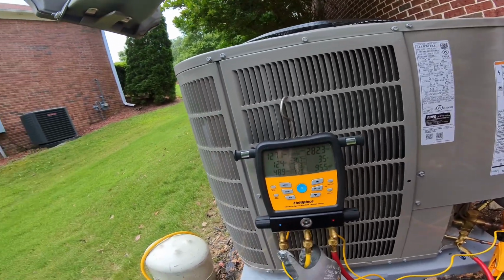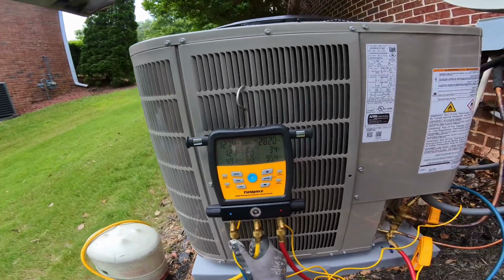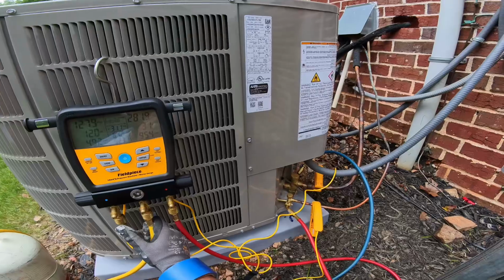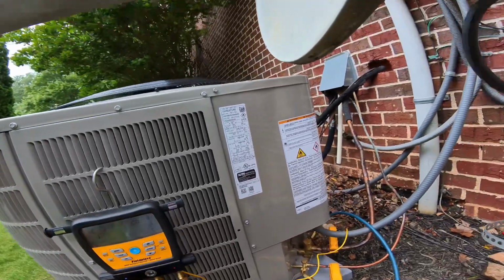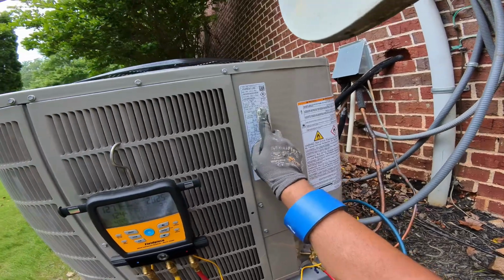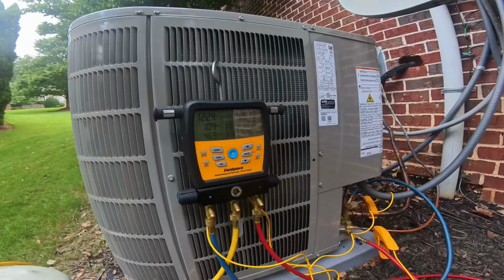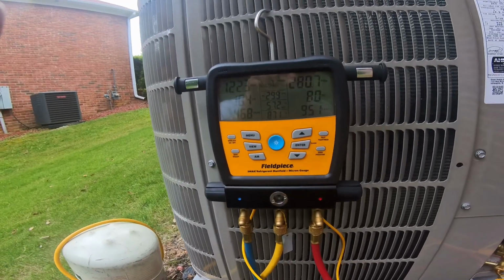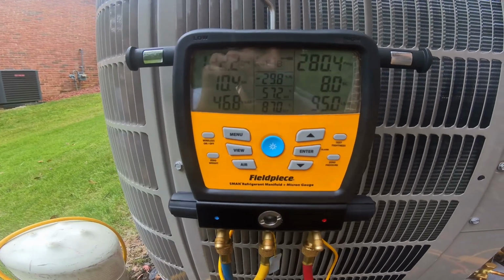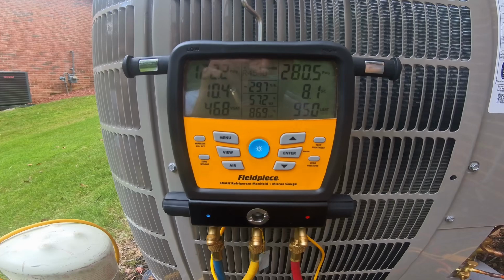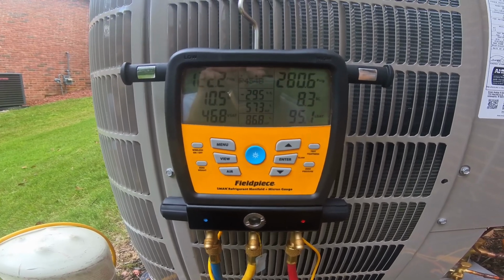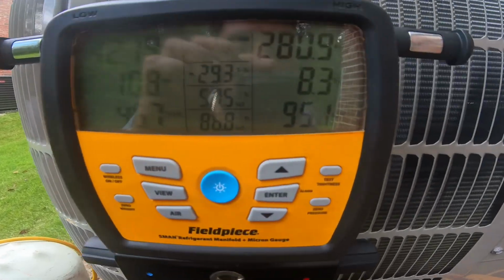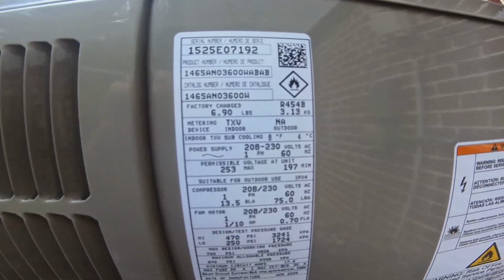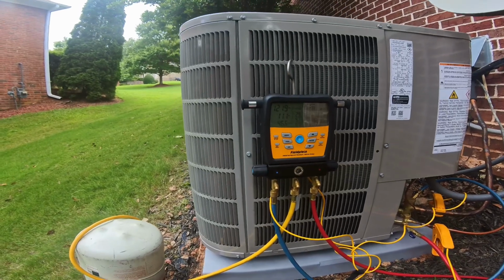Alright guys, these are the pressures we have right now. 454B. I just added some refrigerant, so let's see what we can get this up to. Indoor TXV calls for 8 degrees. We already know we don't have the best airflow inside. Alright, so that's what we have going on. 8 degrees subcool, 10 degrees superheat. Pressures look good. We already know we don't have the best airflow, but at least we got the charge up to where it needs to be. It's 8 degrees. Calls for 8 degrees. So that's it, guys. We'll let her know and we'll go from there.